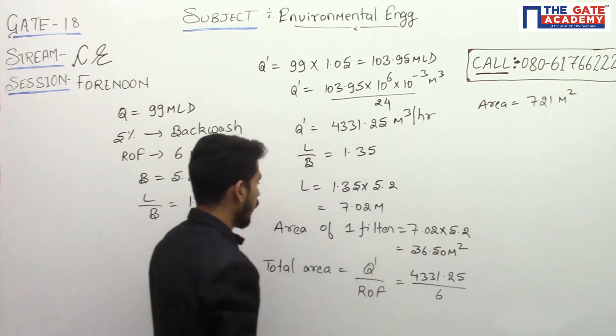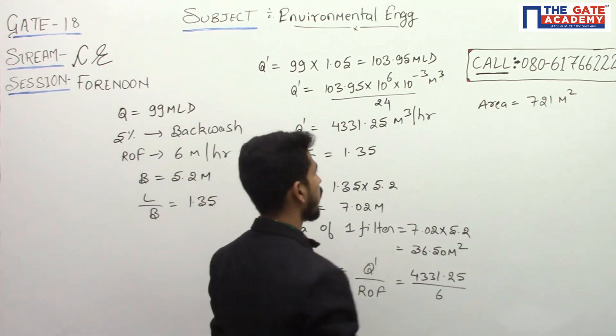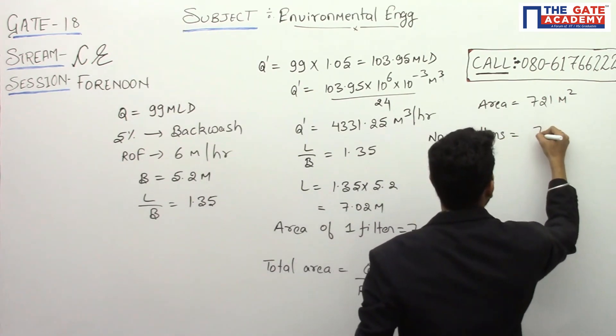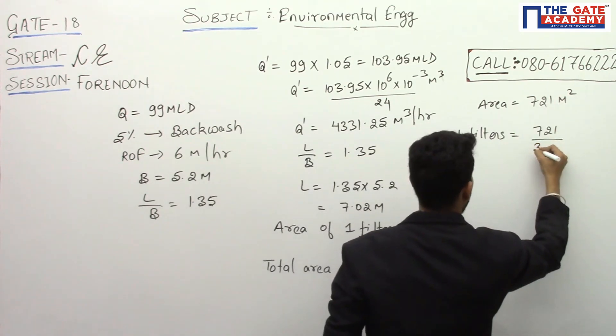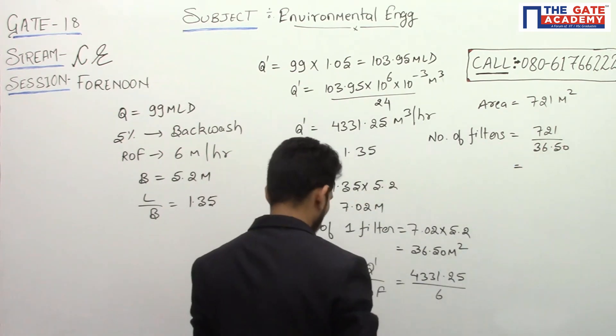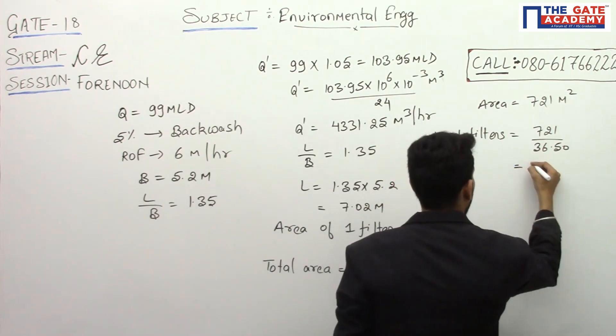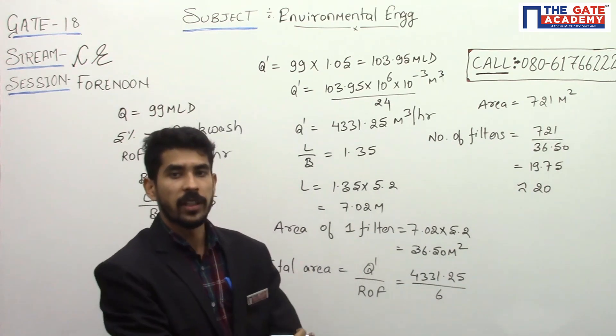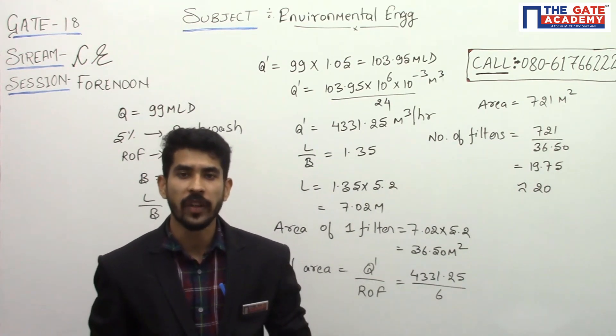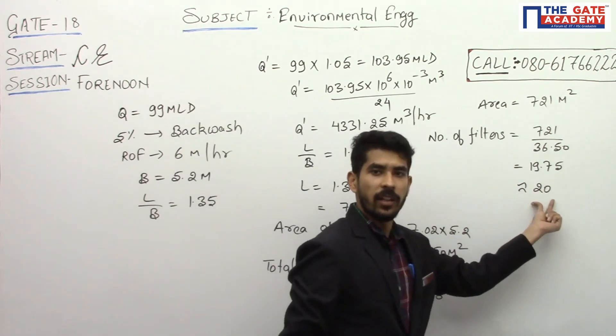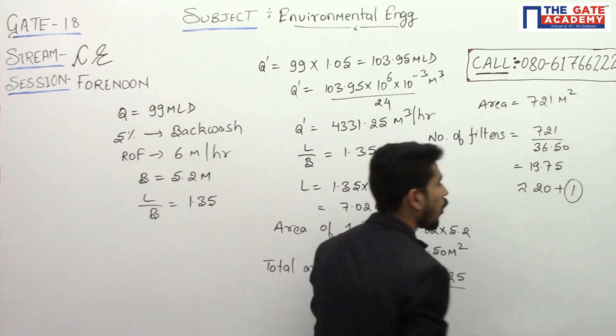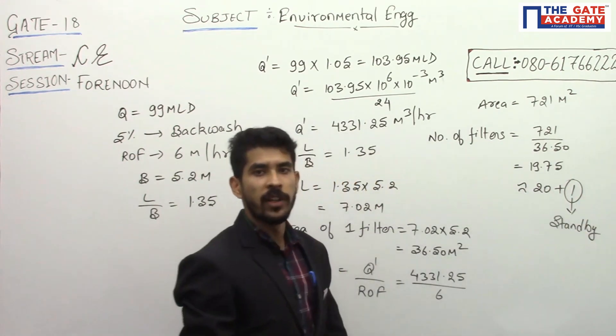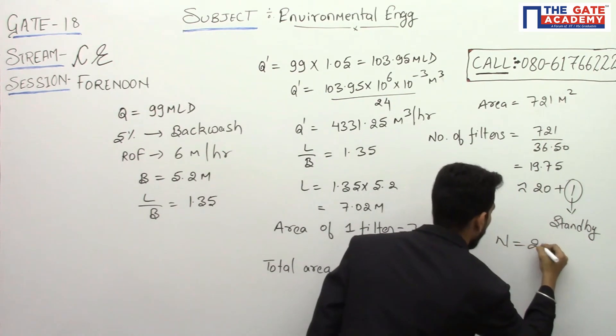We have the total area and the area of one filter, so we can calculate the number of filters. Number of filters equals 721 divided by 36.50, which equals 19.75, approximately 20 filters. But the question states one extra filter is required in case of any breakdown. So 20 are operational filters and one is a standby filter, giving a total of 21 filters.